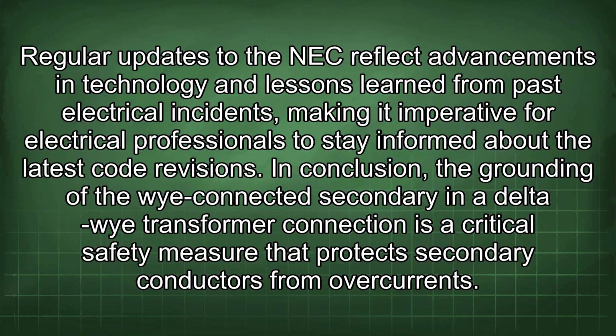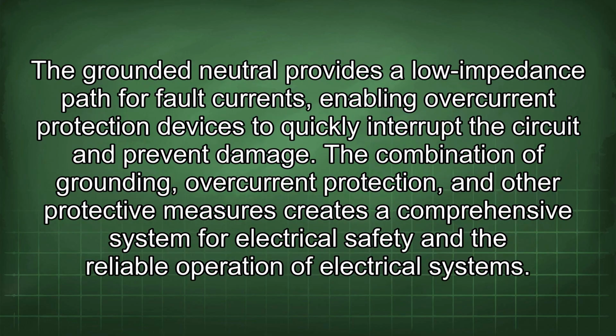In conclusion, the grounding of the Y-connected secondary in a Delta-Wye transformer connection is a critical safety measure that protects secondary conductors from overcurrents. The grounded neutral provides a low impedance path for fault currents, enabling overcurrent protection devices to quickly interrupt the circuit and prevent damage. The combination of grounding, overcurrent protection, and other protective measures creates a comprehensive system for electrical safety and the reliable operation of electrical systems.